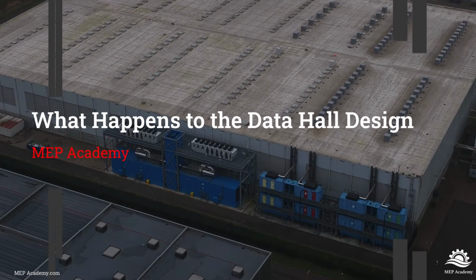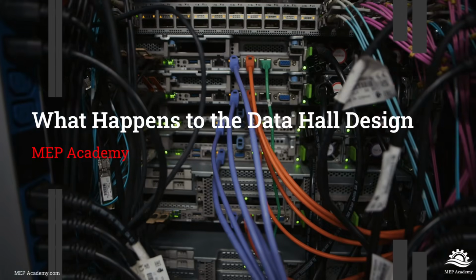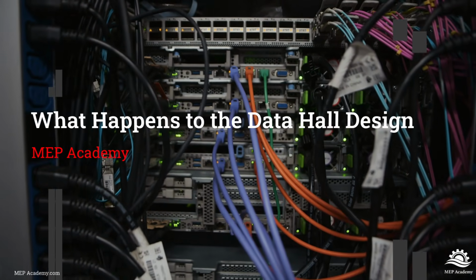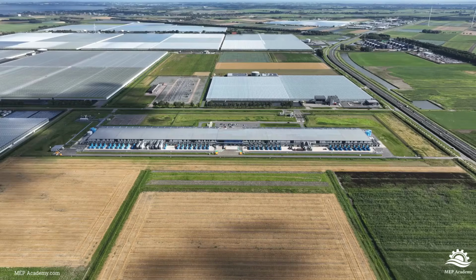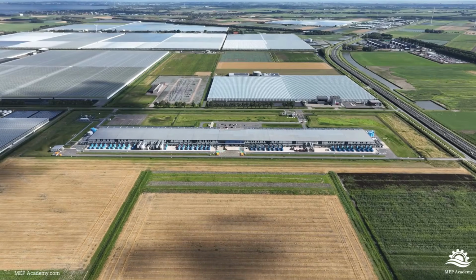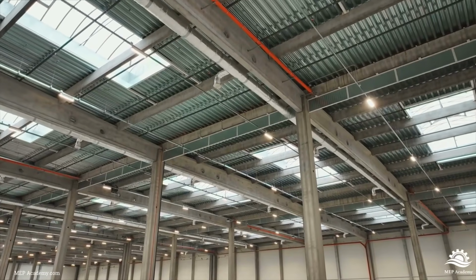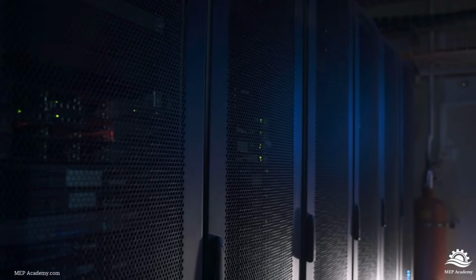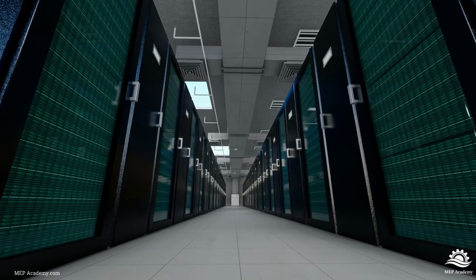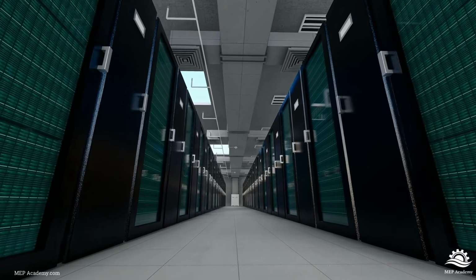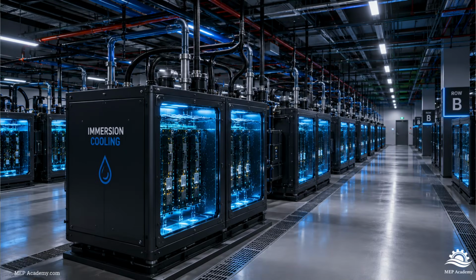This is where things become very interesting from a construction standpoint. Many things we've traditionally associated with data centers may become less important. Hot aisles, cold aisles, perforated floor tiles, massive overhead air distribution systems, entire rows of CRAH units. Some facilities may eliminate many of these components altogether. Instead, you'll see rows of immersion tanks connected to fluid piping networks. In many cases, the building begins to resemble an industrial process plant more than a traditional data center. This is one reason mechanical engineers are becoming increasingly important in AI facility design.